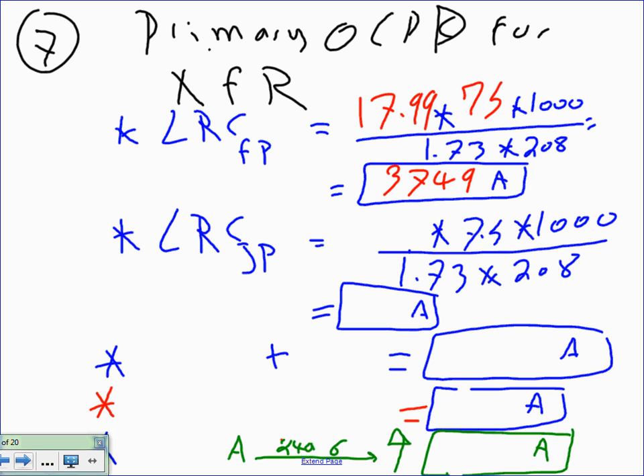3,749 amps is the locked rotor current on this baby. That's a lot of amps. The locked rotor current. It's an S. Is that the S? That's the S letter coded. Yep, the fire pump is an S. S could stand for stupid or smart, or symbol, or whatever you would call it. So that's a lot of locked rotor current. Almost short circuit value. The baby one, guys, was an R.